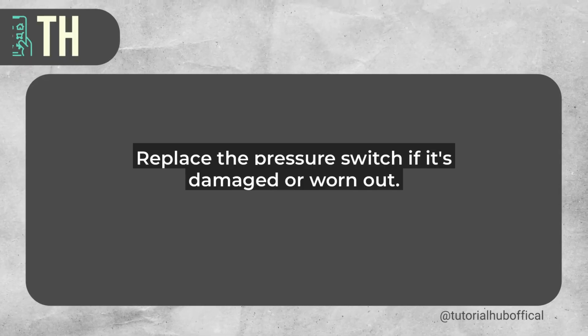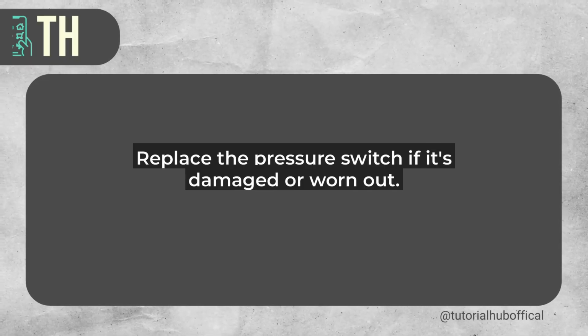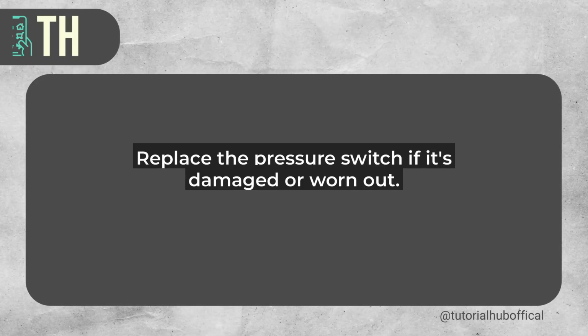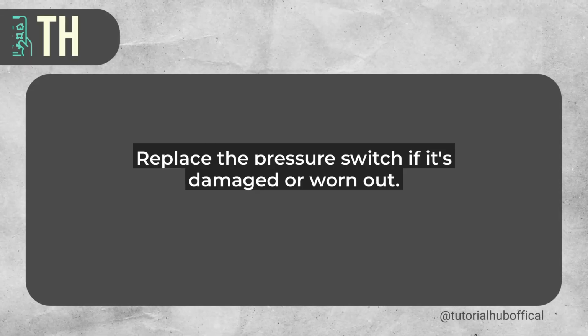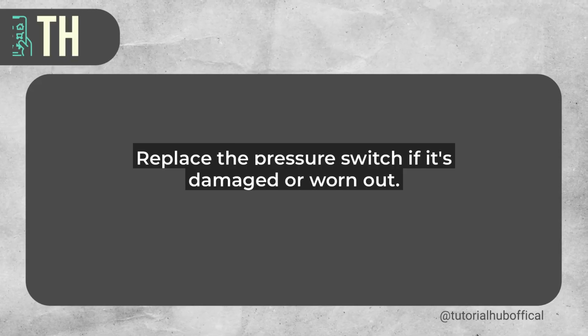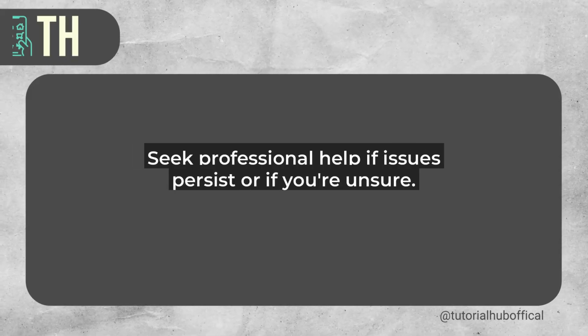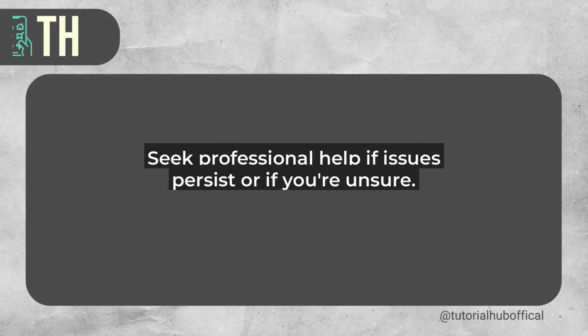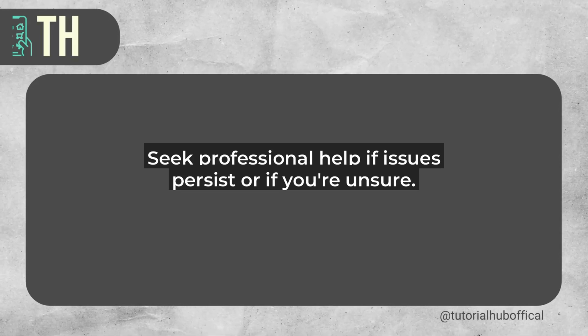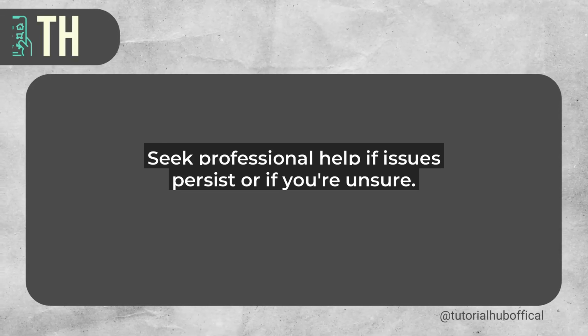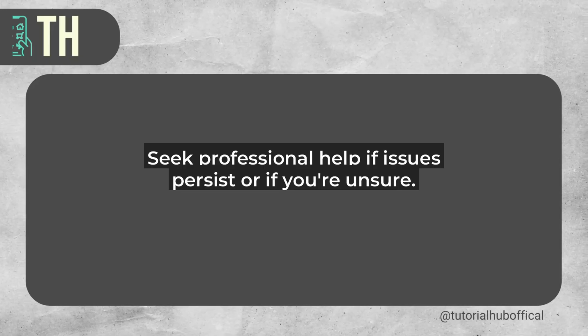After that, reset the furnace by turning the power back on and seeing if the code clears. If the error persists, you might need to replace the pressure switch or check the wiring for any loose connections. Remember, if you're not comfortable with electrical work, it's time to call in a professional HVAC technician. They can diagnose deeper issues and ensure everything complies with safety standards.